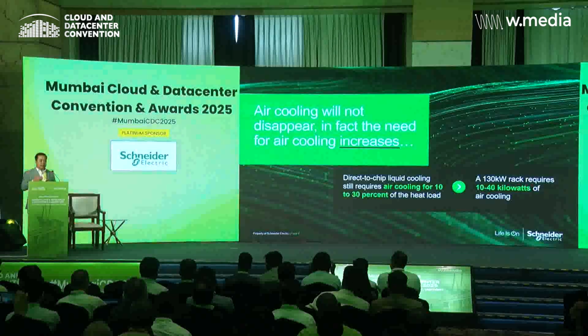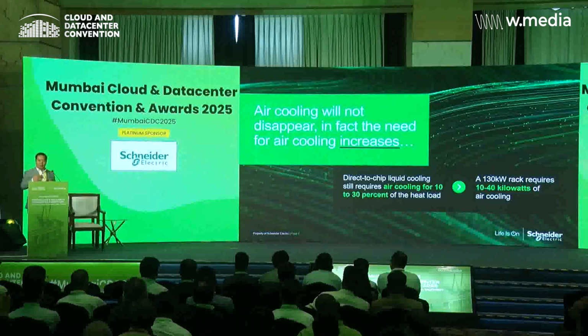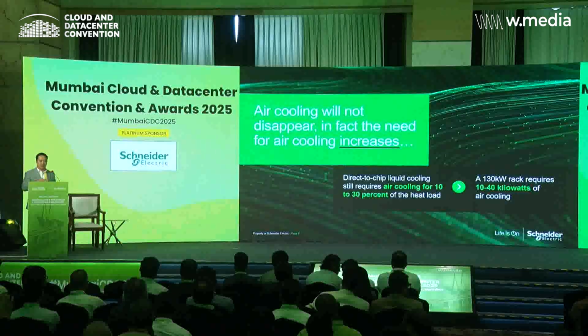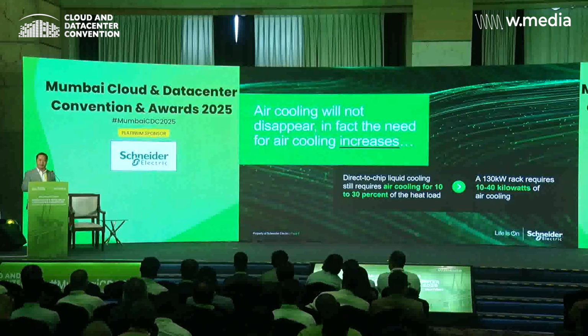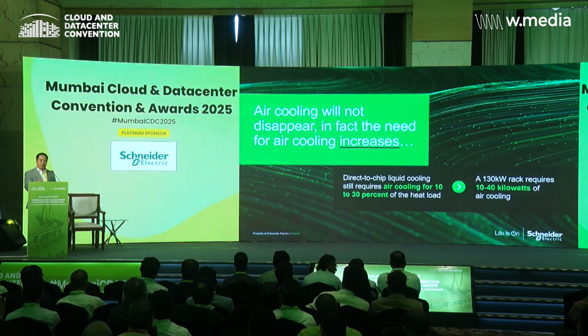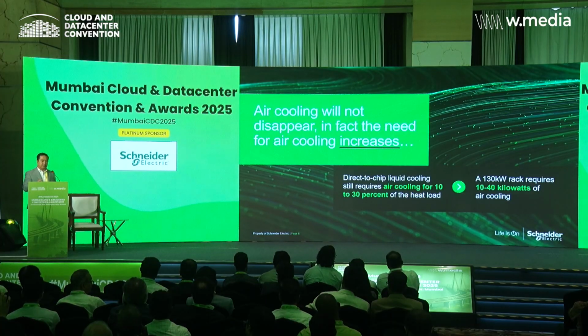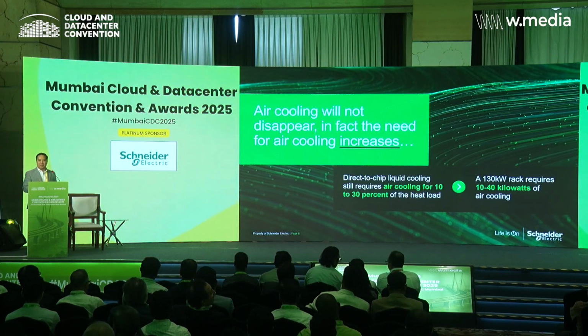You need at least containment if you're going to use room cooling, or you have to use close coupled cooling to really manage that heat efficiently, to make sure that even with liquid cooling, the rest of the server and the pod still work properly and efficiently.